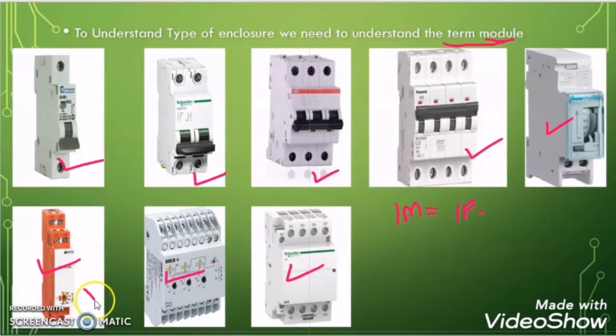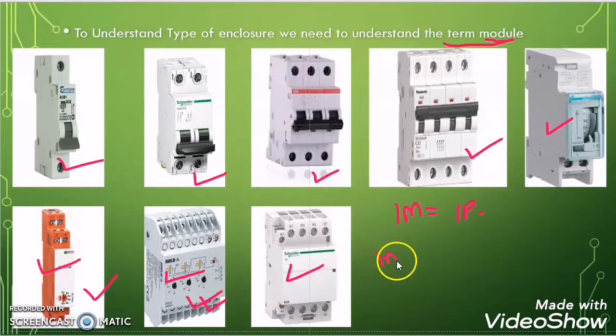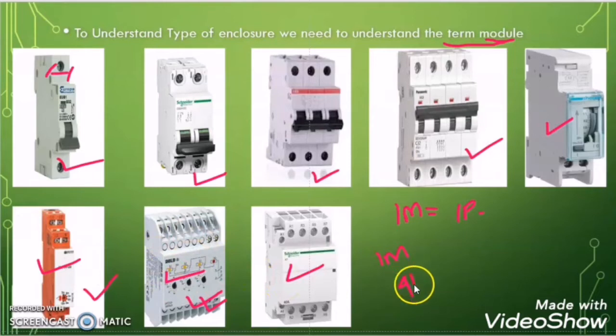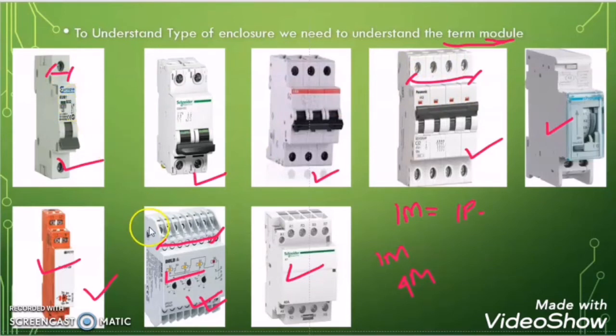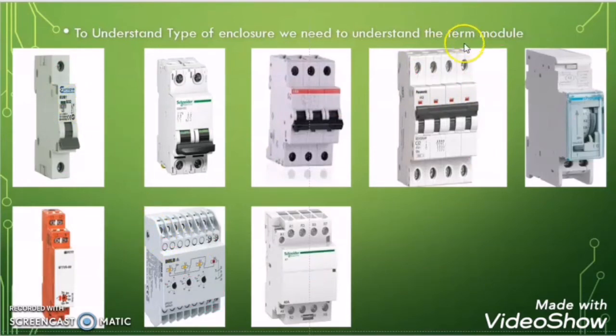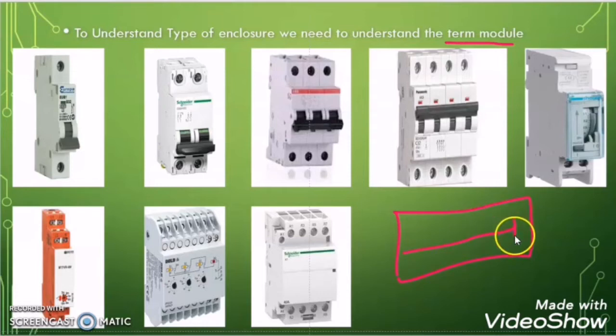In our example, one UV relay is considered as one module because it takes the same space as a single pole MCB. But another UV relay can be considered as four modules because it takes the same space as a four pole MCB or four single pole MCBs. So if someone says a panel of 16 modules, you can imagine that panel has space to install 16 single pole MCBs.